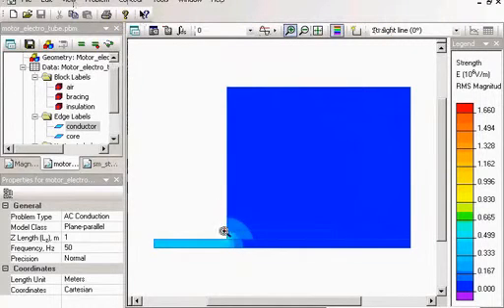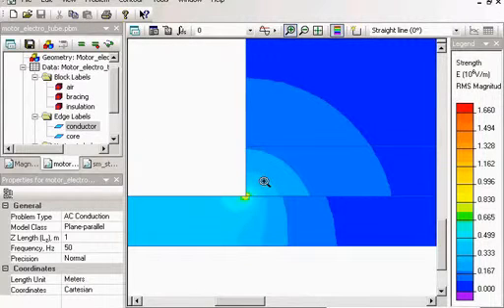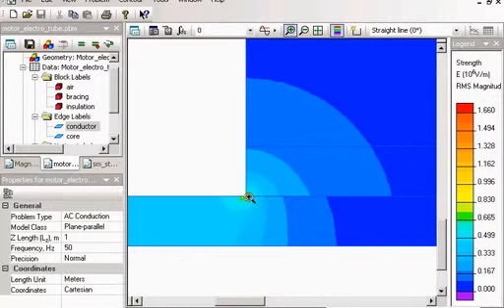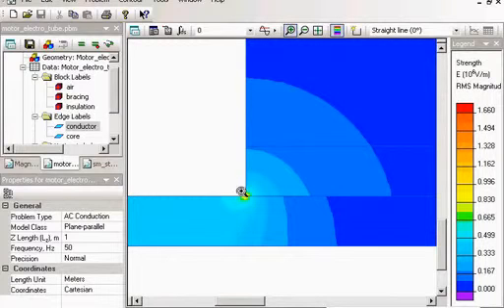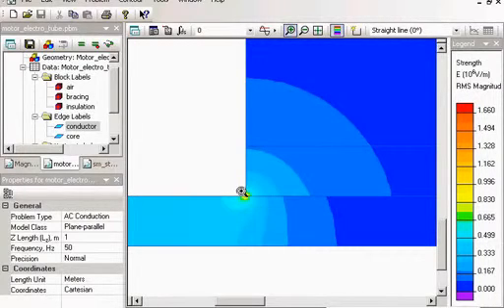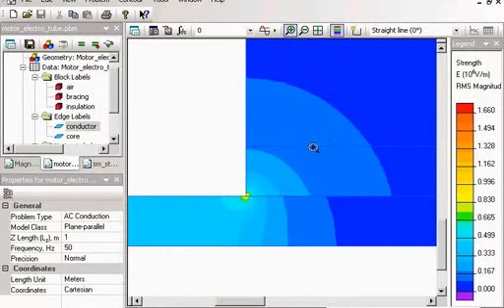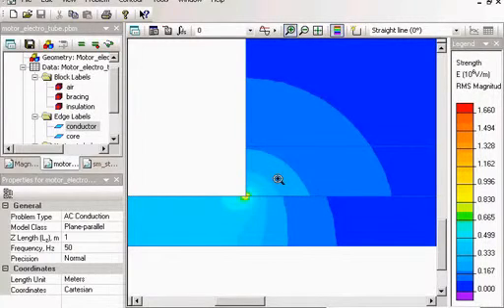You see, when in the place where the stator ends, there is a powerful field distortion and a high electric field strength. And this may cause the insulation to fail in this place. And with QuickField you can simulate such problem and calculate electric field in insulation.